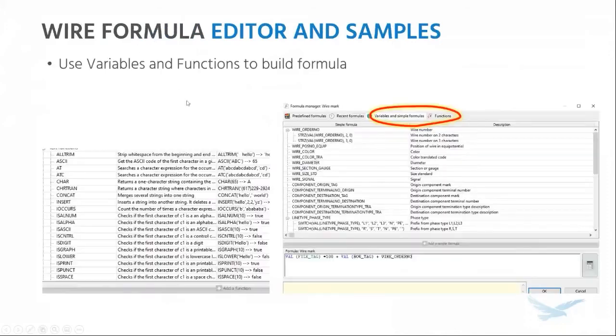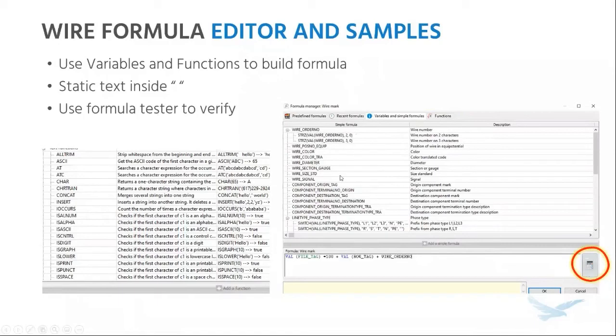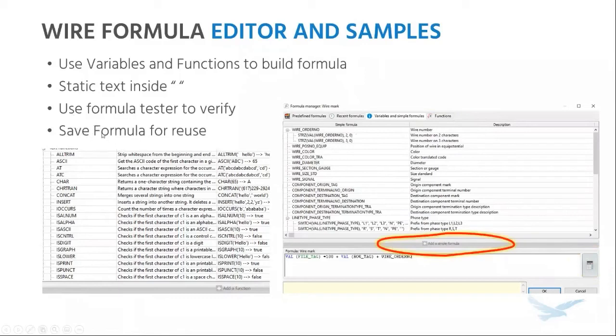The last piece of information on wire styles is the formula editor. There is a wire style editor where you use a combination of variables and functions to build custom formulas. The variables you would see for a wire style formula builder are very different from those for a row numbering formula builder. There's also a list of functions with descriptions and examples. If you intend on putting any static text inside the formula — like a dash or space — all of that goes inside double quotes. There's also a formula tester to verify the formula gives you what you want. Go ahead and save those formulas in the project in case you want to reuse or play around with them later.